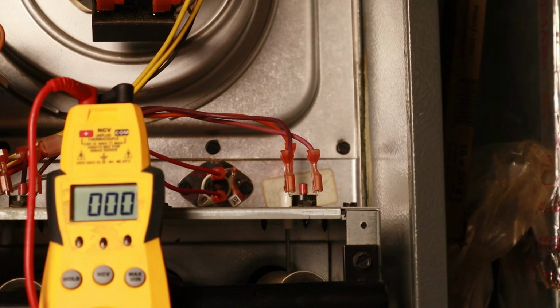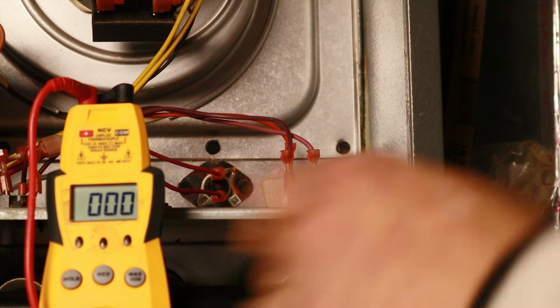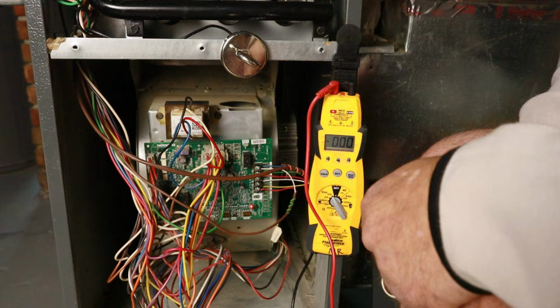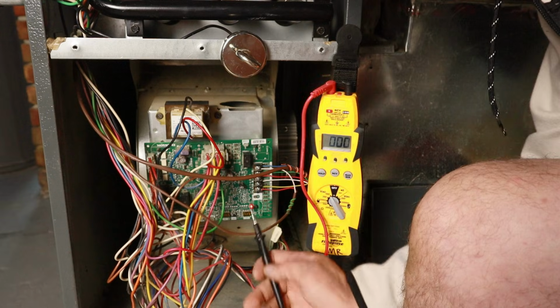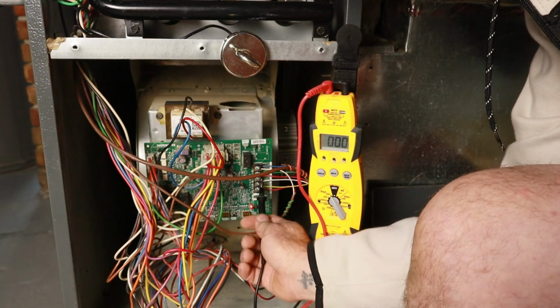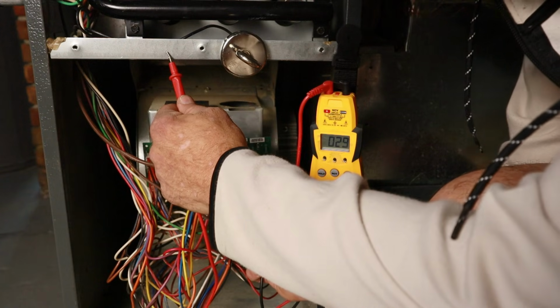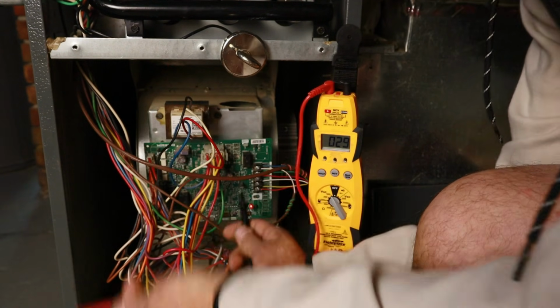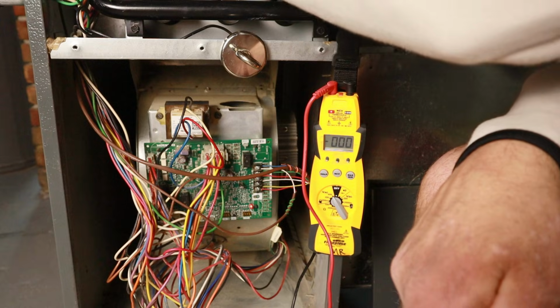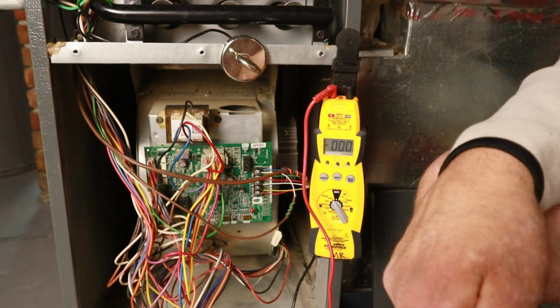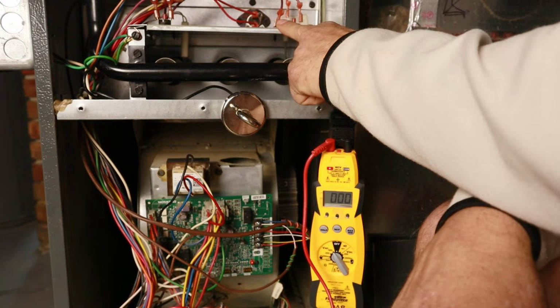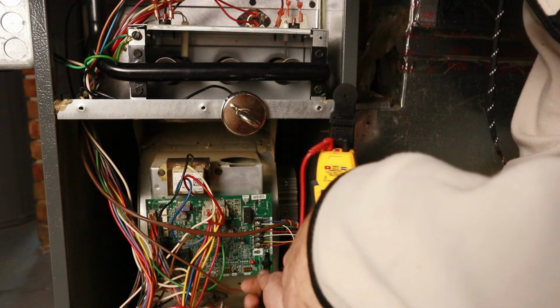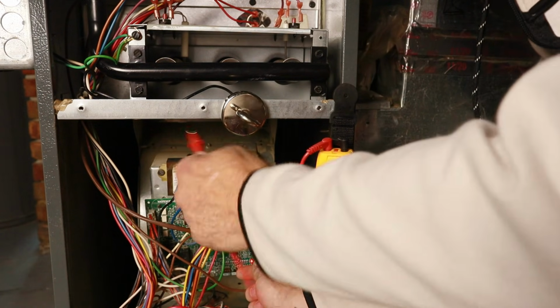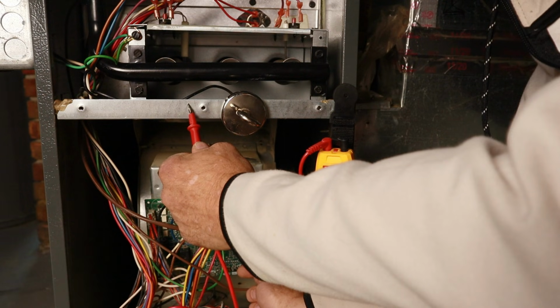So if you do ever test the R terminal on your control board and you're not seeing power there, but you have power at your fuse, one of these limits is most likely triggered. So if I go ahead and test for 24 volts at this R terminal here, I should read voltage if everything is okay. And I am reading 29 volts there. Now watch what happens when I unplug one of these. I took that wire off of the flame rollout there. Now you can hear my blower turned on. That's a safety feature. But if I go ahead and test again for 24 volts at that R terminal, I am not reading anything.